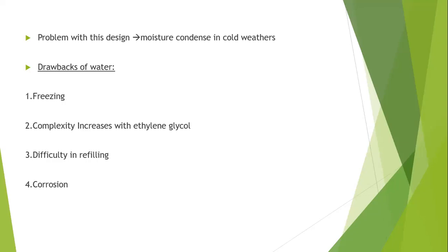This corrosion problem can be minimized by using copper tubes, but it is somewhat costly. Economically, we can use aluminium for tubes. Though aluminium is less expensive, if aluminium tubes are used, the water has to periodically undergo chemical treatment.